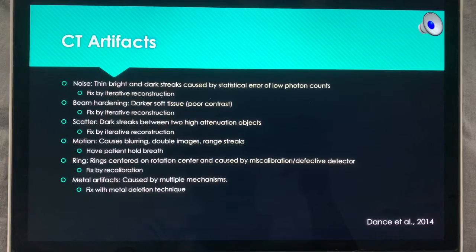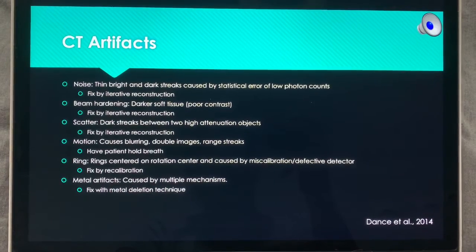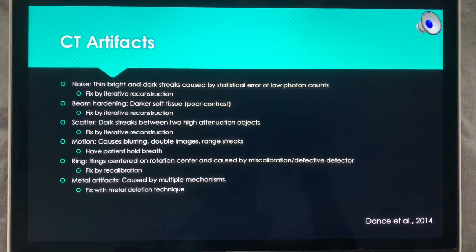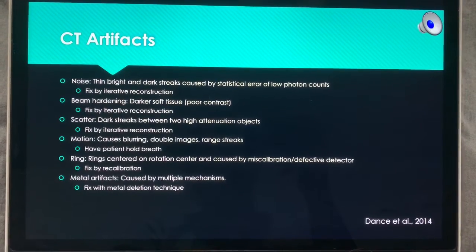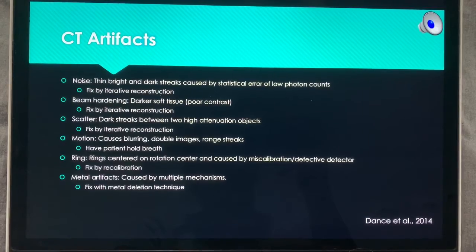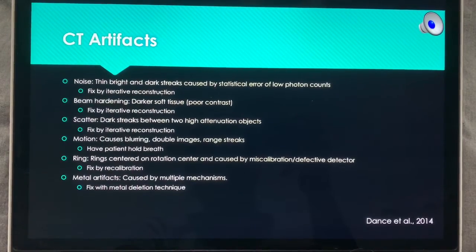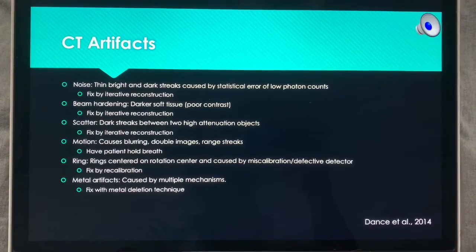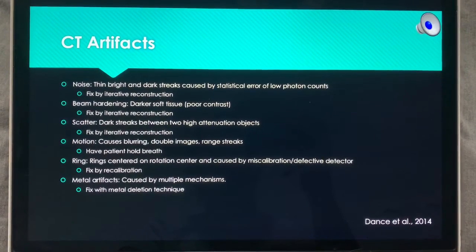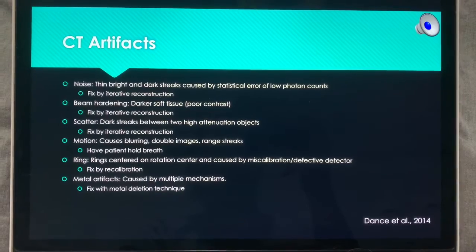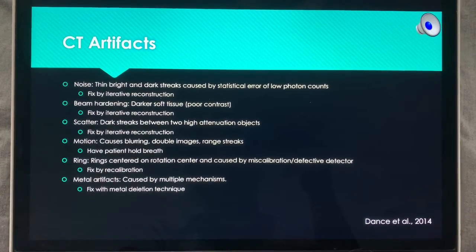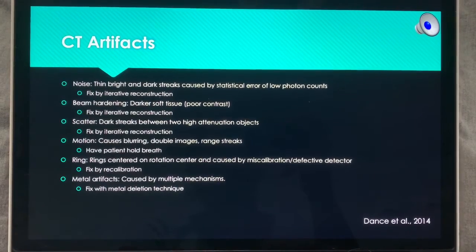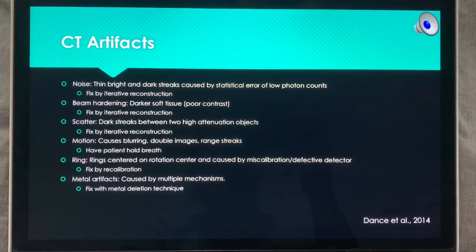In computed tomography, CT, the term artifact is applied to any systematic discrepancy between the CT numbers in the reconstructed image and the true attenuation coefficients of the object. CT images are inherently more prone to artifacts than conventional radiographs because the image is reconstructed from something on the order of 1 million independent detector measurements. The reconstruction technique assumes that all of these measurements are consistent, so any error of measurement will usually reflect itself as an error in the reconstructed image.